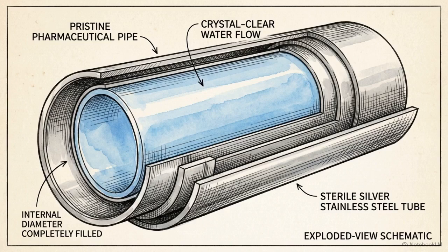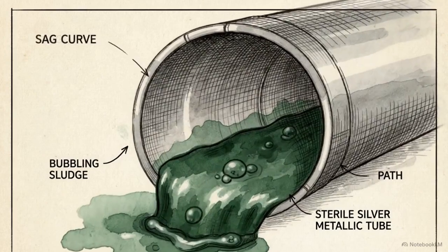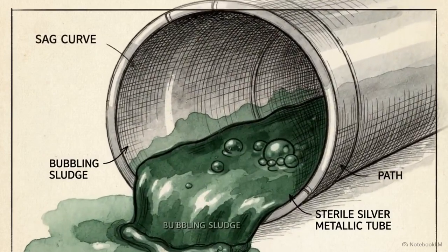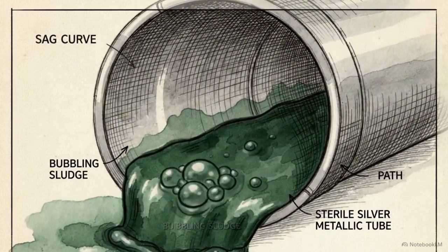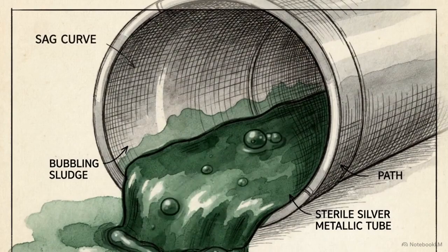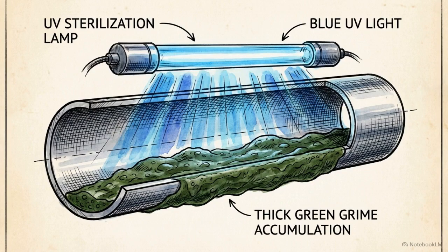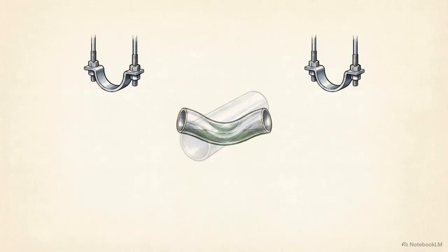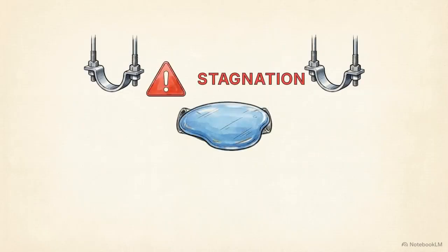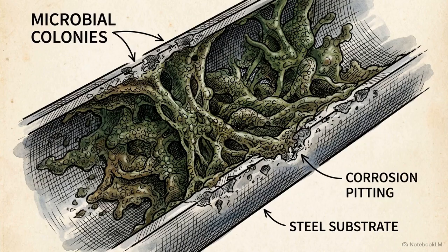High-purity water systems require constant motion to remain sterile. When flow slows in a compromised line, a bacterial sludge known as biofilm can quickly take hold of the interior steel. Filtration and UV sterilization are standard, but they cannot overcome stagnation. If water is allowed to pool in a flat or sagging section of pipe, bacteria form colonies that are difficult to remove with standard chemical cycles.